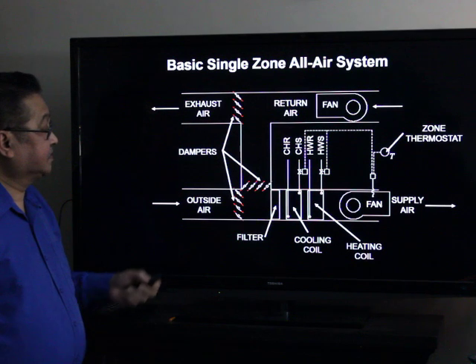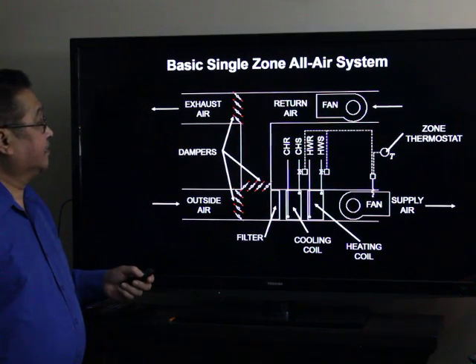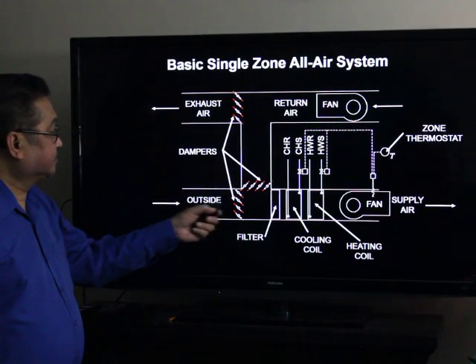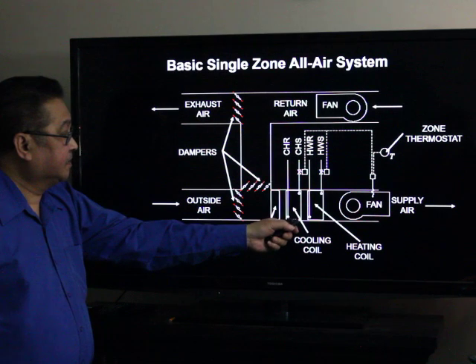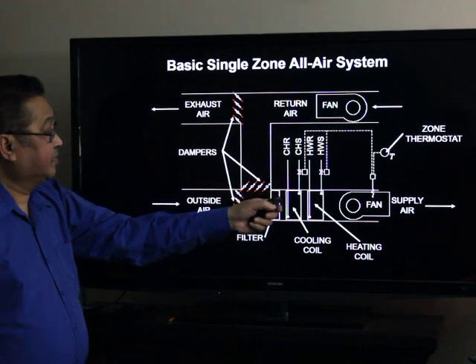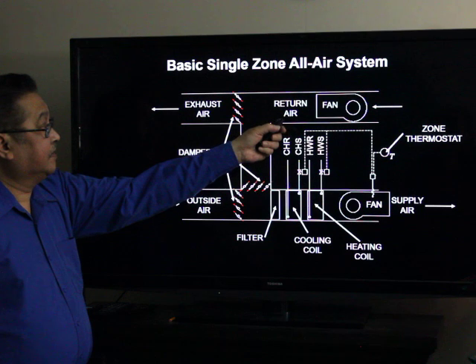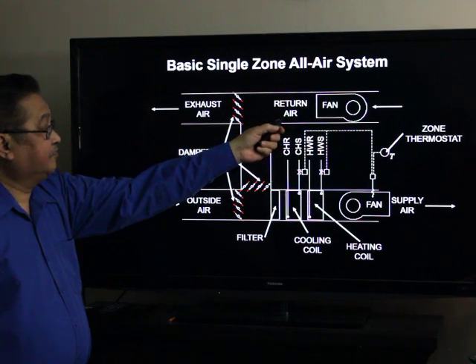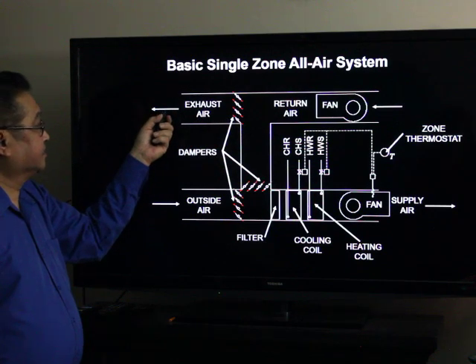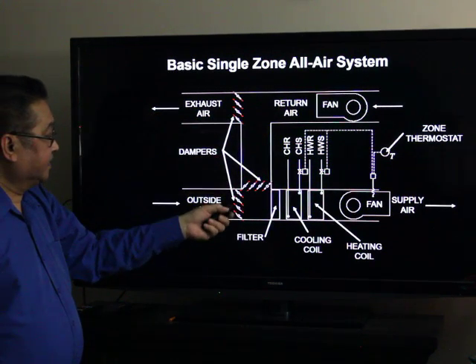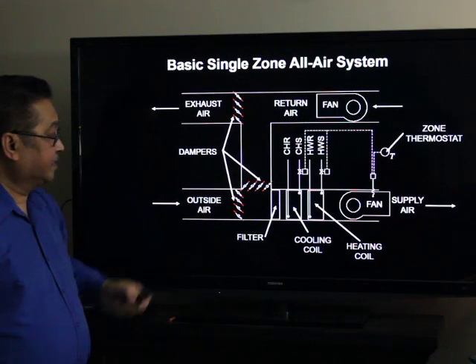This is an illustration of the basic single zone all air system. We have here the outside air going through the filter, cooling coil, heating coil, and the supply air fan, going to the zone. And you have the return air fan, which is interlocked with the supply air fan, going to the exhaust air, with part of it being returned to mix with the outside air.